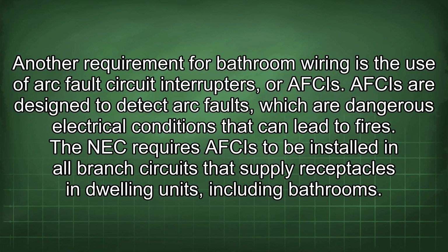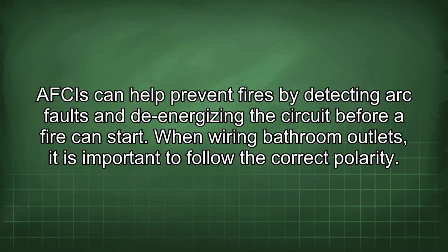Another requirement for bathroom wiring is the use of arc fault circuit interrupters, AFCIs. AFCIs are designed to detect arc faults, which are dangerous electrical conditions that can lead to fires. The NEC requires AFCIs to be installed in all branch circuits that supply receptacles in dwelling units, including bathrooms. AFCIs can help prevent fires by detecting arc faults and de-energizing the circuit before a fire can start.